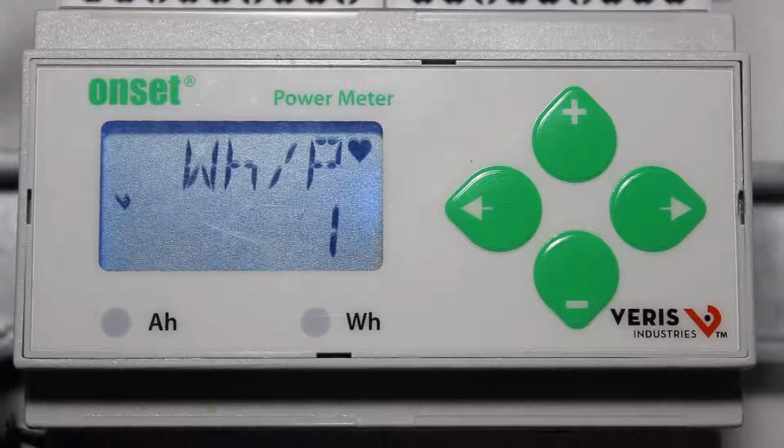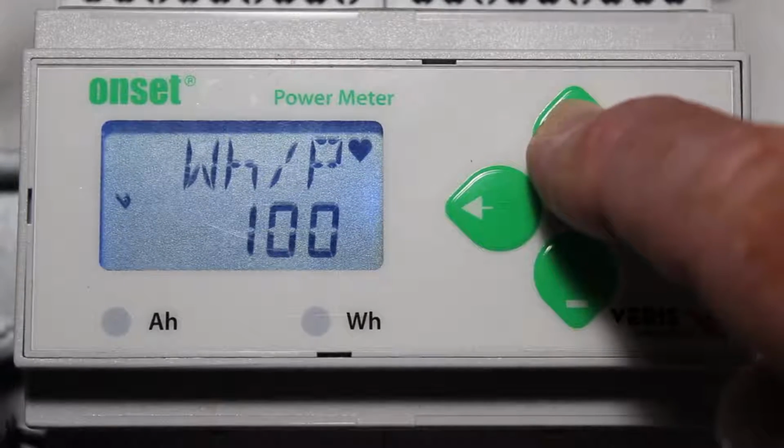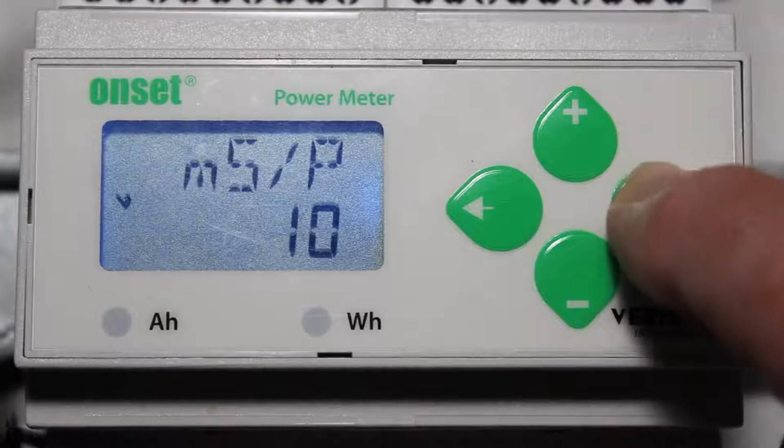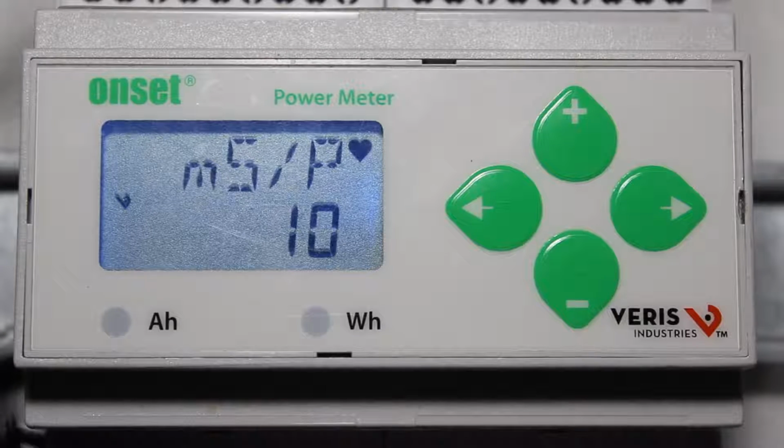Watt hours and VAR hours per pulse are basically linked: when you set watt hours, you're also setting a pulse weight for VAR hours. So for this application, we do want 1. They will go up in increments of 10, so if it was 10 or 100, you can change that. Right arrow. One thing that can be confusing in the manual is that the menu displays our amp hours setting as milliamp hours to cut down on the number of decimal places displayed on the LCD. So in the manual it may say 0.001 amp hours, that's 1 milliamp hour. So that's what we're going to use here. This is correct. The other setting you can change is the milliseconds per pulse, which is the pulse width. There are explanations in the manual about why you want to change that, but for this we're not going to.